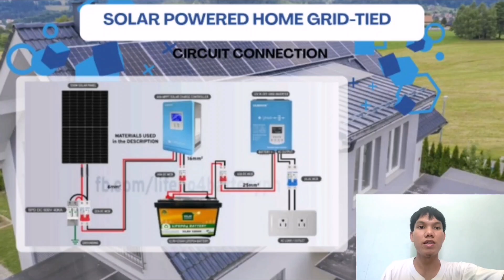Next, from this diagram, the setup shows energy beginning at the solar panels, passing through a DC breaker into the solar charge controller to maintain the health of your battery bank. What makes this system unique is the integration of the grid-tied inverter with a limiter. As we see in this wiring, there is a physical connection to the limiter sensor, a clamp near the main utility entrance. This sensor acts as a traffic controller. It tells the inverter exactly how much solar power to release so that you maximize your free energy without accidentally sending any back to the grid and getting billed for it.